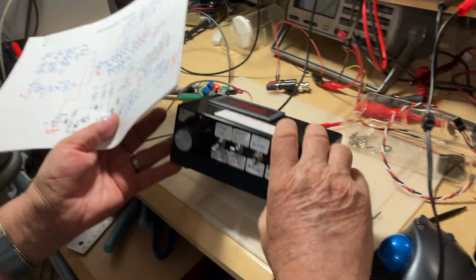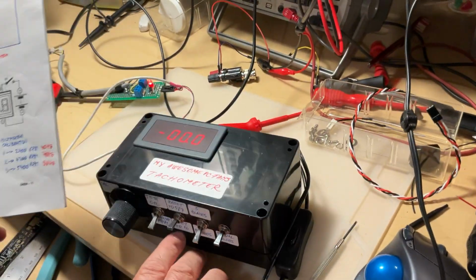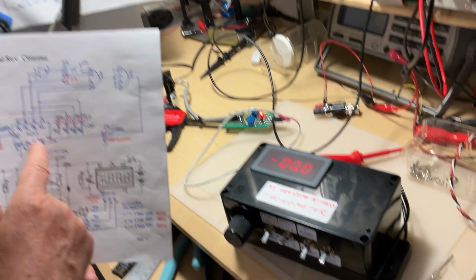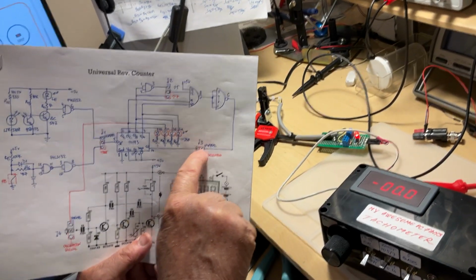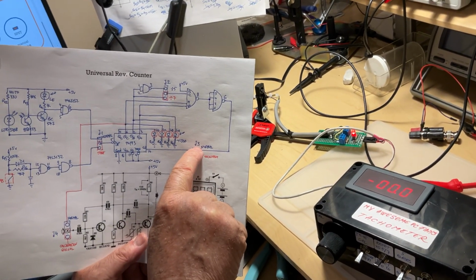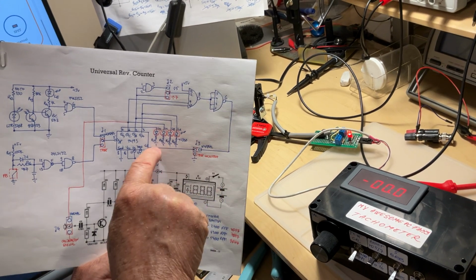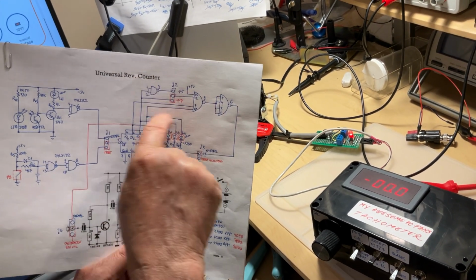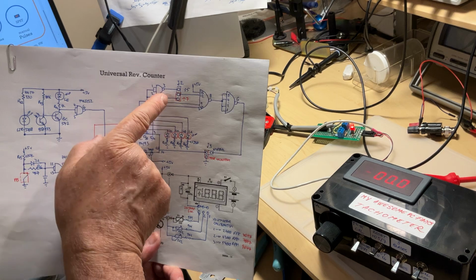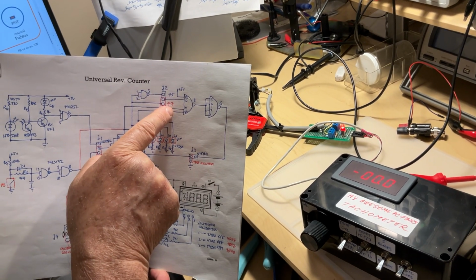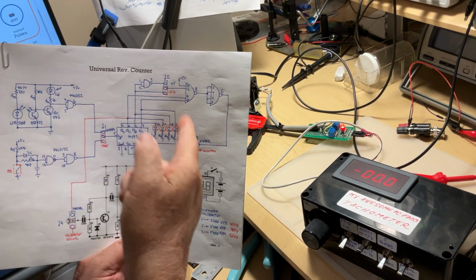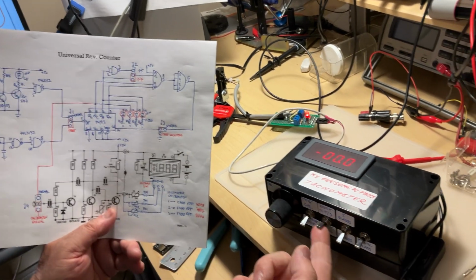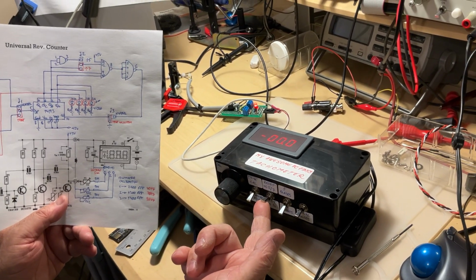This is why here it says reset to 16, because the counter has 16 positions, 0 to 15. But if the jumper is put on that horizontal position here, then the signal for the reset comes from that little decoder, and that little decoder, having two options, 5 or 7 blades, is going to stop the counting at 5 or at 7. So it's important when you measure to have this reset to 5 and 7.